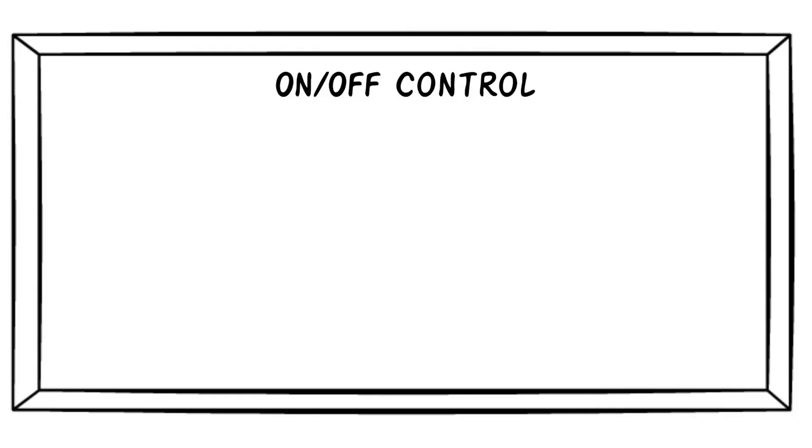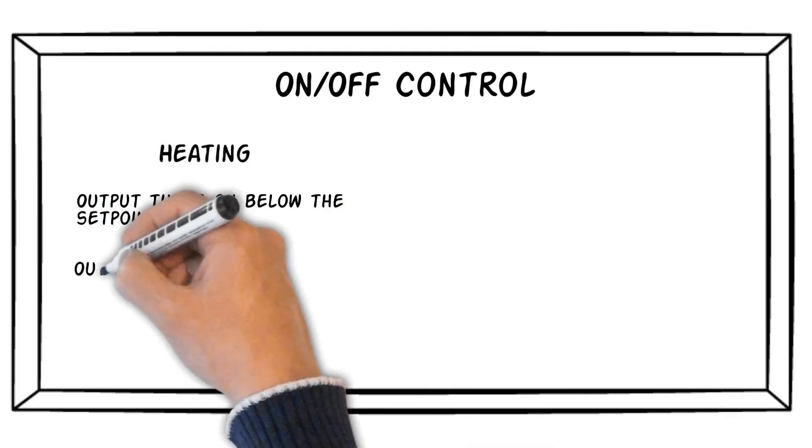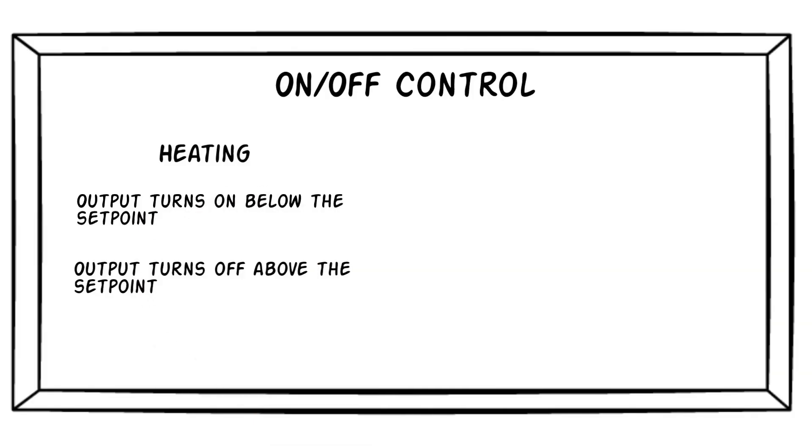When using on-off control in a heating application, the output turns on below the set point and turns off above the set point. This means if the output is connected to a heater, the heater will turn on when the temperature is below the set point and turn off when the temperature is above the set point. This is referred to as indirect acting control.